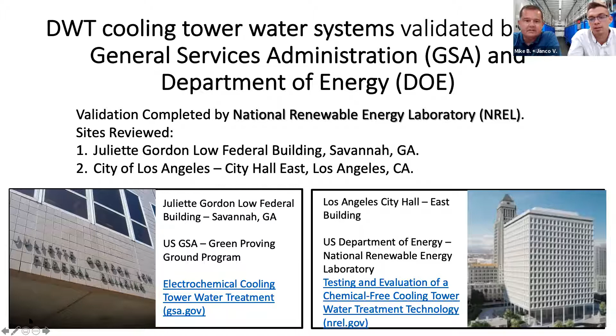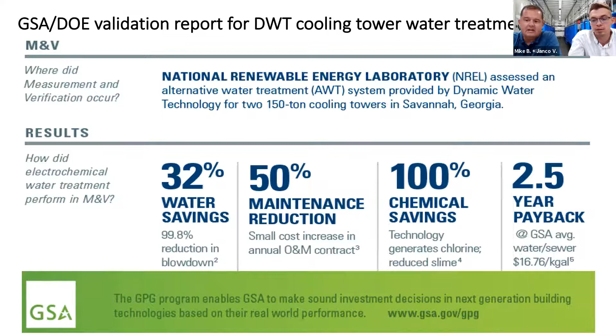The first review, achieved from the GSA on the federal building in Savannah, Georgia, showed a net water savings of about 32% in overall makeup water, a reduction in overall maintenance because there was no chemical treatment to do whatsoever, and much less biologic buildup because we're sanitizing the water at a much more effective rate. There was a 100% elimination of chemicals and a calculated payback of 2.5 years.